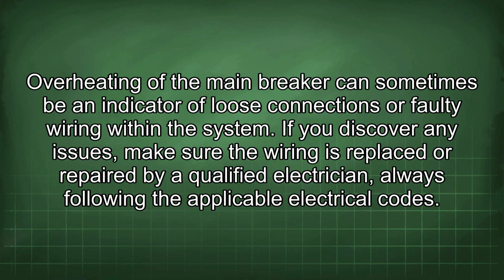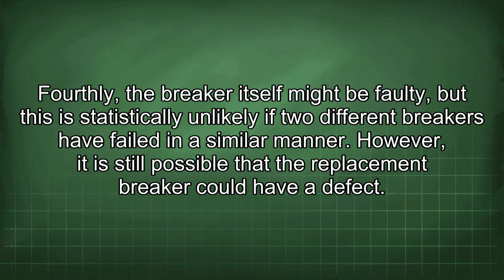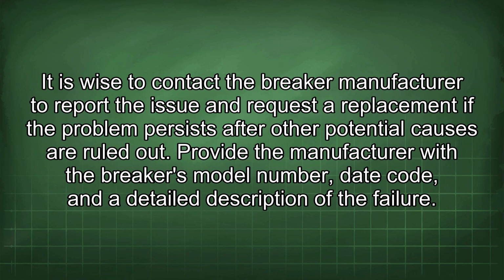applicable electrical codes. Fourthly, the breaker itself might be faulty, but this is statistically unlikely if two different breakers have failed in a similar manner. However, it is still possible that the replacement breaker could have a defect. It is wise to contact the breaker manufacturer to report the issue and request a replacement if the problem persists after other potential causes are ruled out. Provide the manufacturer with the breaker's model number, date code, and a detailed description of the failure.